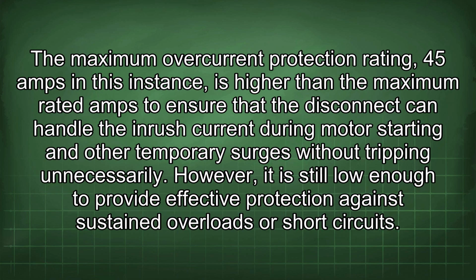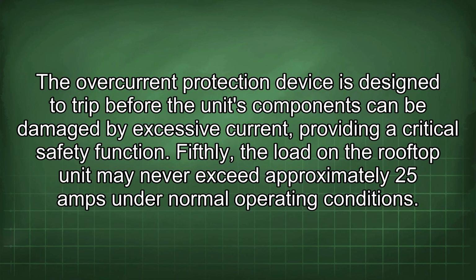The maximum overcurrent protection rating, 45 amps in this instance, is higher than the maximum rated amps to ensure that the disconnect can handle the inrush current during motor starting and other temporary surges without tripping unnecessarily. However, it is still low enough to provide effective protection against sustained overloads or short circuits.